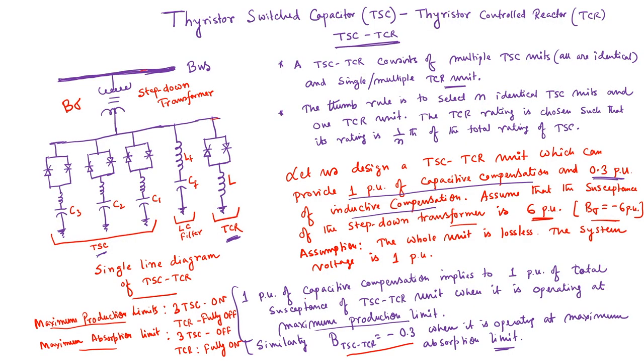That corresponds to BTSC-TCR equal to minus 0.3. Whenever this one per unit of capacitive compensation applies, at this particular operating condition when it is operated at maximum production limit, BTSC-TCR is equal to 1 per unit. Now, based upon that, we need to design the reactance value of the reactor of the TCR unit and also the capacitances of the capacitor unit.